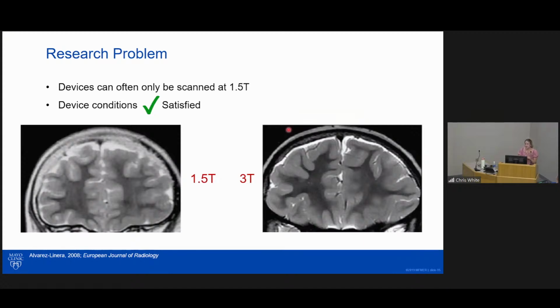So again, many patients that need an MRI scan have implanted devices, and these devices can often only be scanned at 1.5 T in order to satisfy manufacturer conditions. 3T MRI is the preferred field strength used to image the brain because of the increased image quality compared to 1.5 T, as seen in these 2 figures. However, 3T scanning is more restrictive for implanted devices because of the higher field strength. Therefore, it's not available for many patients with implanted devices. And this is again because most implanted devices are made from metal, which is going to create problems when introducing them into the MR environment.